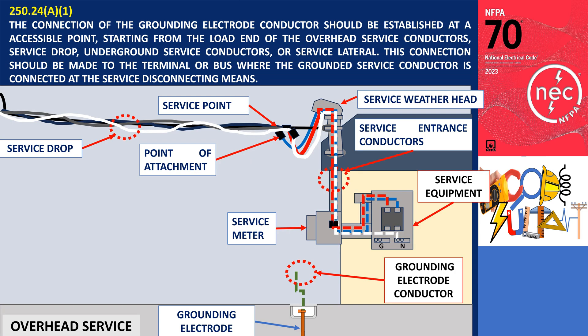The connection of the grounding electrode conductor should be established at an accessible point, starting from the load end of the overhead service conductors, service drop, underground service conductors, or service lateral. This connection should be made to the terminal or bus where the grounded service conductor is connected at the service disconnecting means, as per subsection 250.24(a)(1).